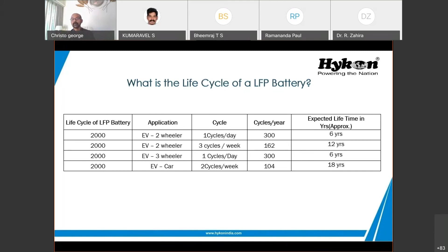The second parameter affecting the life of the battery, besides cycles, is the discharge rate. If you are discharging the battery at 1C, that is 100% discharge, your life is 2000 cycles. That's the cycle they are saying. I'm taking the LFP case. But if you are discharging only 50% of the battery, then the cycle will increase to 5000.